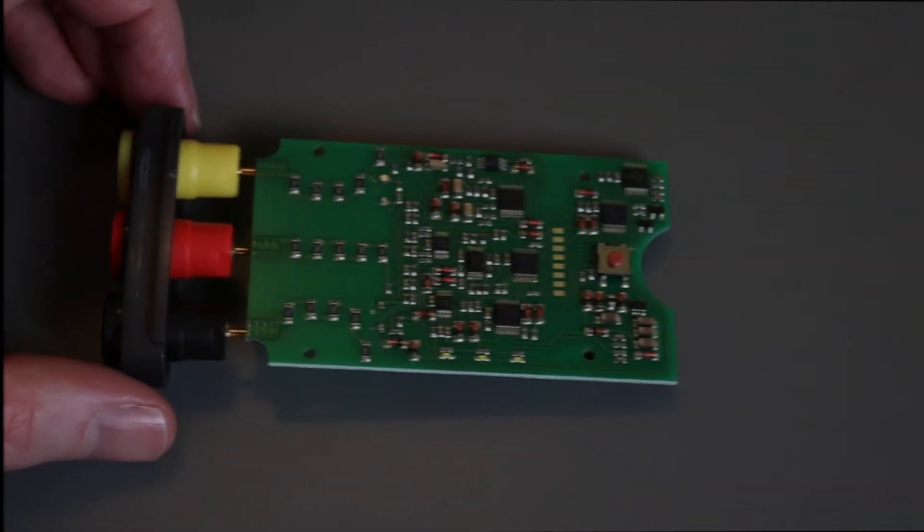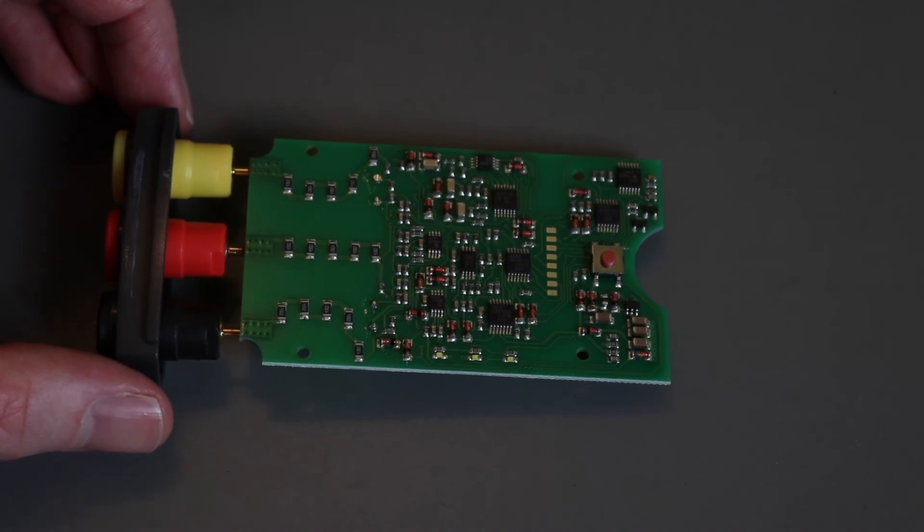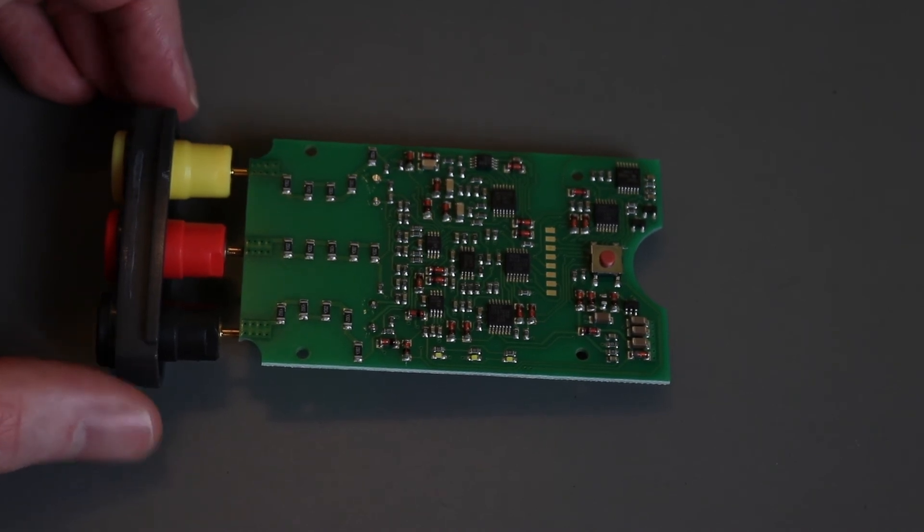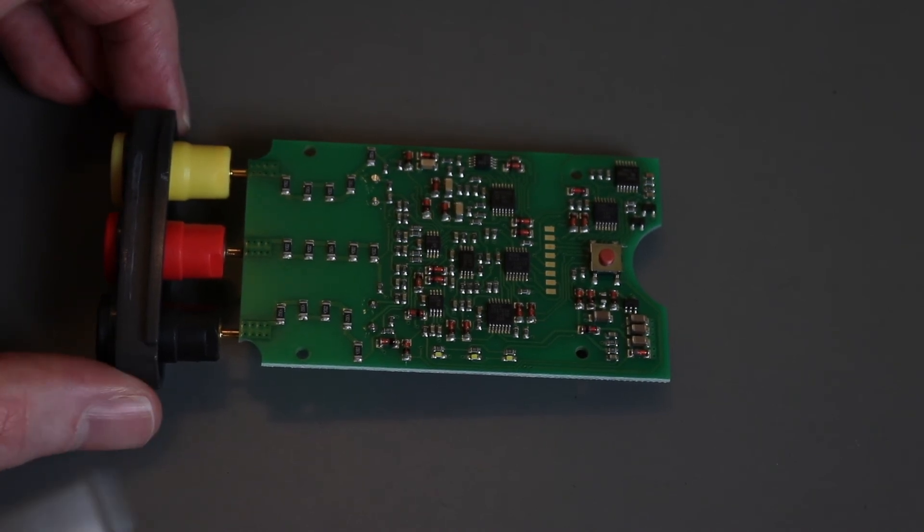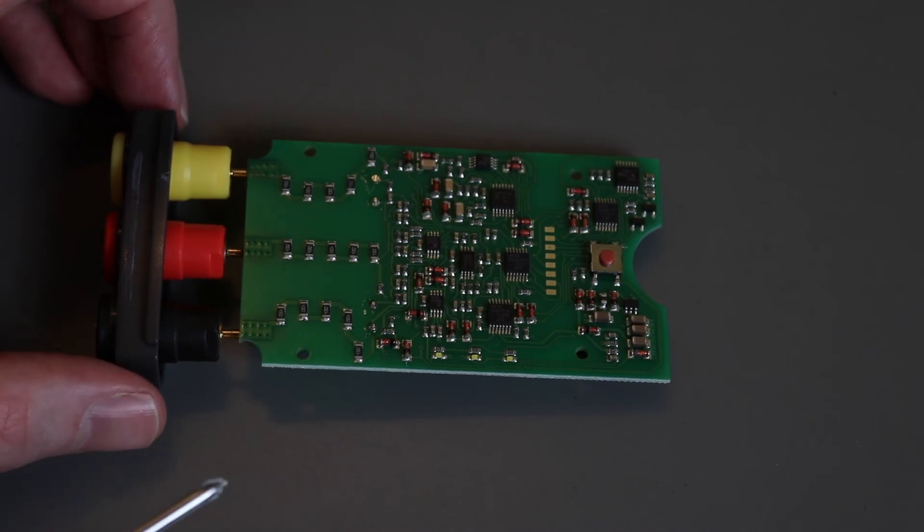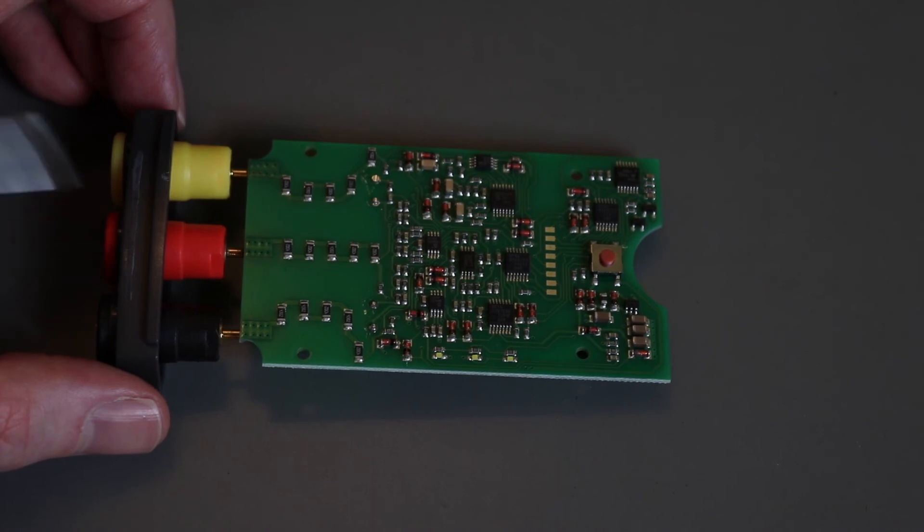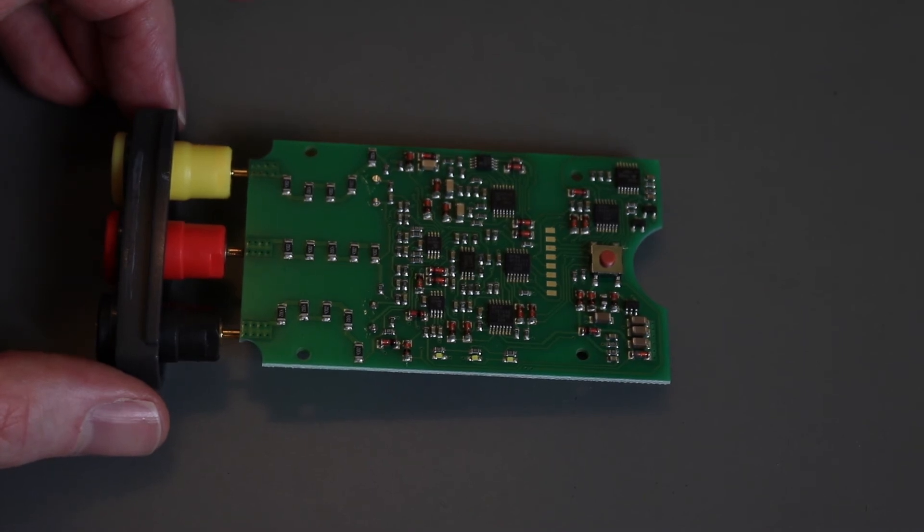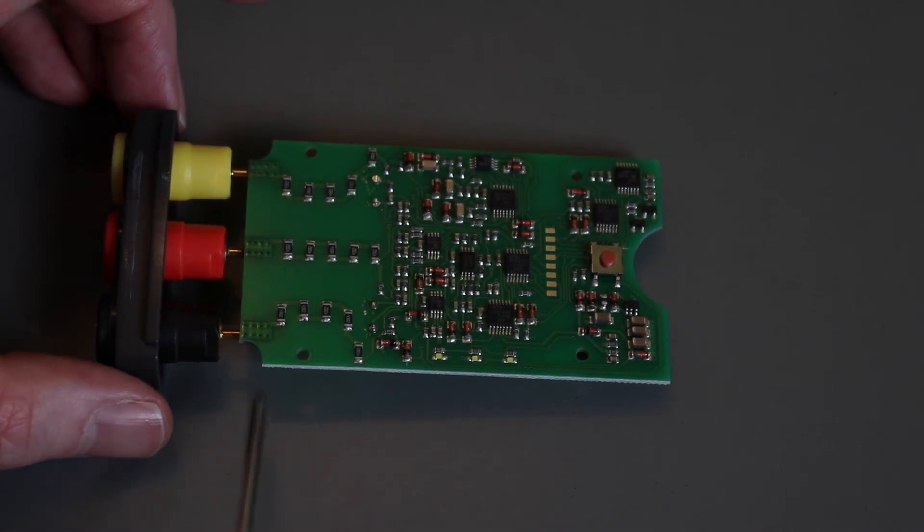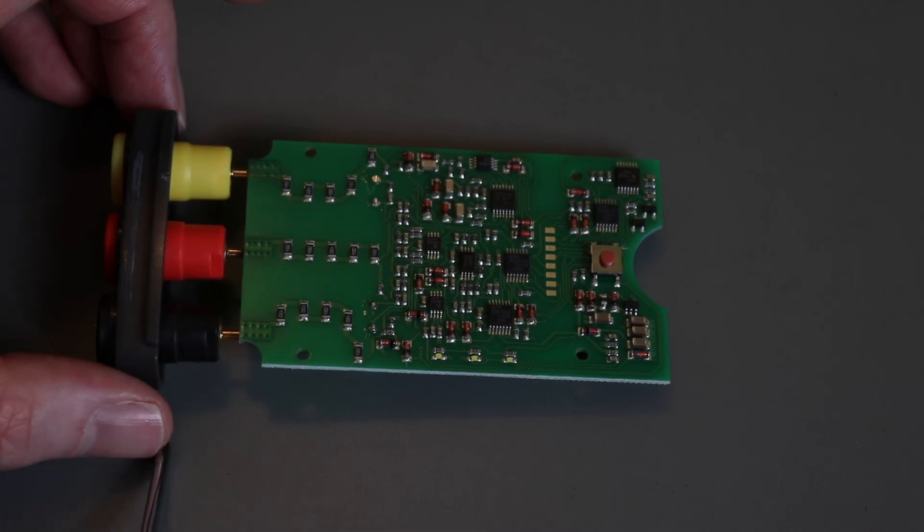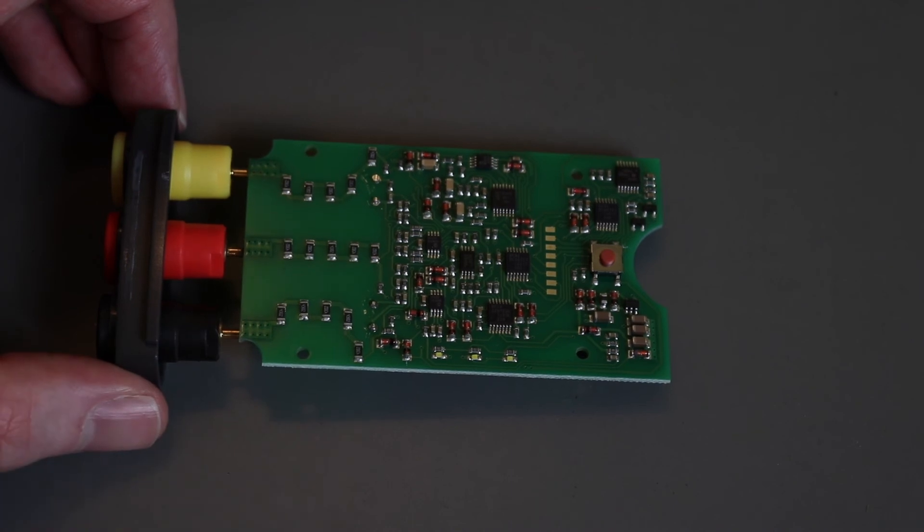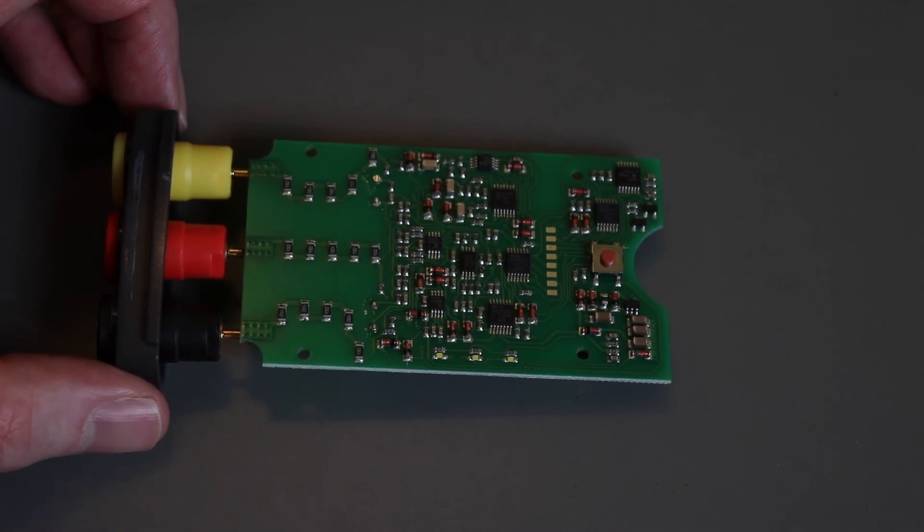Here we are with the Amprobe unit. Unlike the other two units, this unit is actually CAT 4 600 volts. Again, I can't really see an awful lot of difference between the input on this and the input circuits on the other two. You can see there's a fair bit of space between each of the input jacks, and then straight on, even more obvious, onto the dropper circuits made up of multiple resistors before disappearing into the electronics. Down here is your on/off button for the actual instrument.